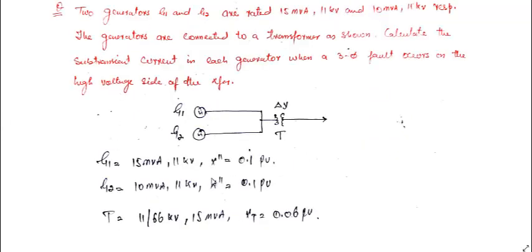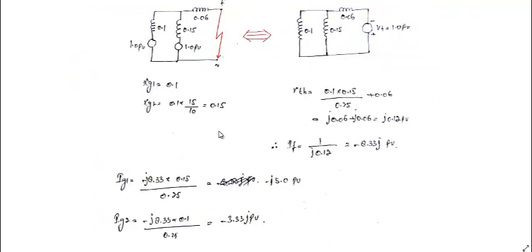The equivalent circuit shows two generators in parallel — generator one and generator two — with the fault between the fault point and neutral. Take base at 15 MVA, 11 kV. The reactance of generator one (0.1 per unit) stays unchanged since it is already on this base. Generator two's reactance changes: using the change-of-base formula, 0.1 × (15/10) = 0.15 per unit. The transformer reactance is 0.06 per unit.